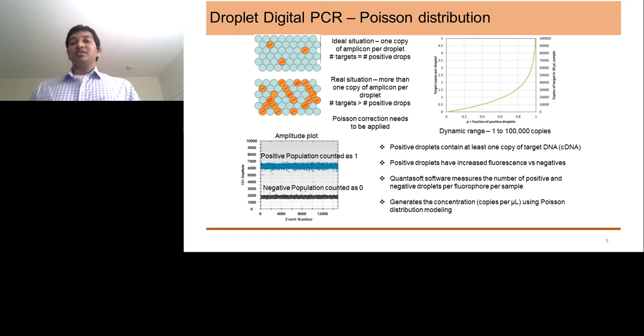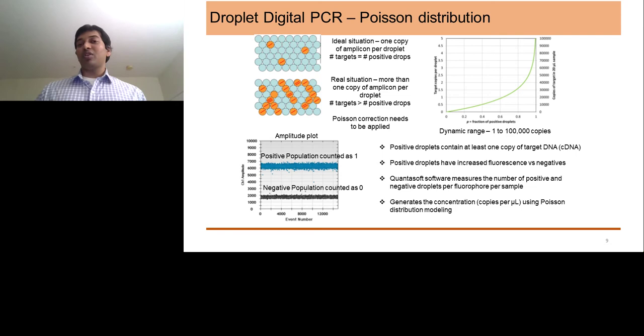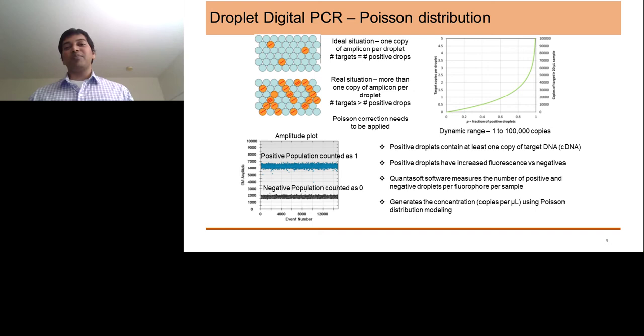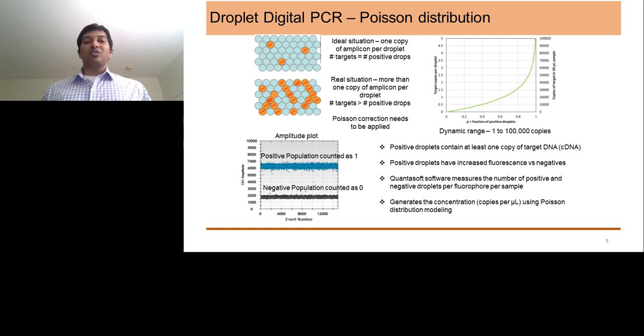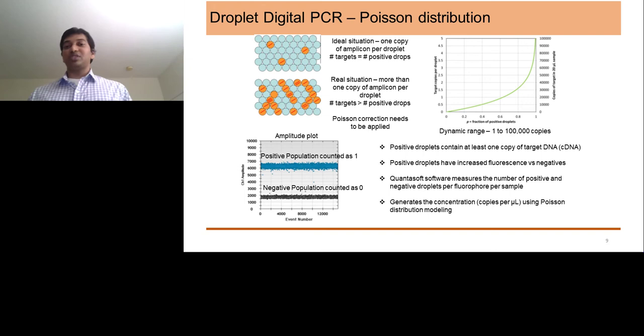Digital Droplet PCR has a high dynamic range, meaning it can go even to a very low copy number — it can read around one copy per reaction. Once the Droplet PCR is complete, you get an amplitude plot with a positive and a negative population. The negative population is counted as zero and positive as one. Droplets with at least one copy are positive, and more than one copy is also positive. As you increase the template, the positive droplets have higher fluorescence intensity compared to negative, which is where you see the distribution of these two populations.